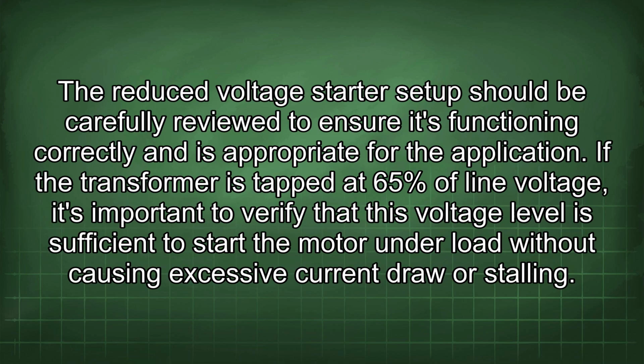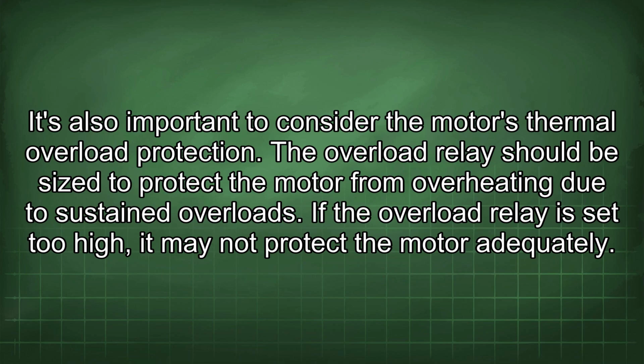The reduced voltage starter setup should be carefully reviewed to ensure it's functioning correctly and is appropriate for the application. If the transformer is tapped at 65% of line voltage, it's important to verify that this voltage level is sufficient to start the motor under load without causing excessive current draw or stalling. It's also important to consider the motor's thermal overload protection. The overload relay should be sized to protect the motor from overheating due to sustained overloads. If the overload relay is set too high, it may not protect the motor adequately.